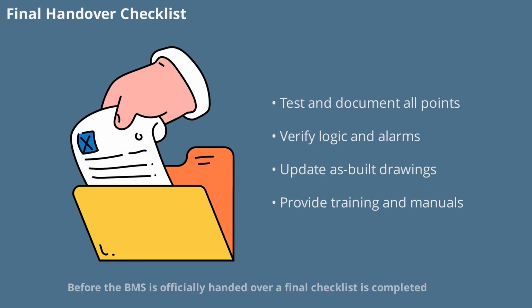Before the BMS is officially handed over, a final checklist is completed. All points are tested and documented, logic and sequences are verified, and alarms and graphics are confirmed functional. The I/O list and drawings are updated to reflect as-built conditions. User training is provided, a maintenance manual is delivered, and all software backups are submitted. This comprehensive checklist ensures the client receives a fully operational and well-documented system.